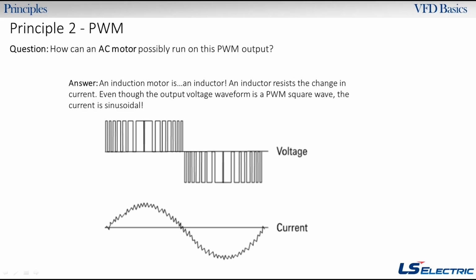So the motor is still running off of an AC current waveform, and the voltage is going to be that PWM waveform. So 99% of the time when you look at a motor, or if you're selling a motor, it's going to be an inverter duty rated motor. And the inverter duty rated motors are able to run off this PWM waveform. So they run a little hotter. There's some little transients here and some voltage spikes. But if you order an inverter duty motor, which is what most people are running now, it'll run perfectly okay off of this signal. So there's nothing to worry about.